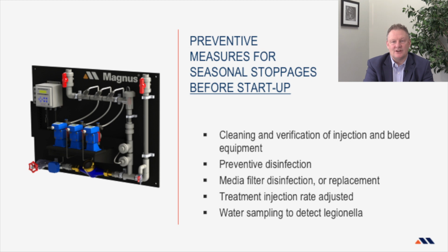Once the system is restarted, it is important to disinfect with an oxidant, such as chlorine or bromine. Stagnant water left over in the system may have biofilm, which must be removed before startup, as it can become a location for Legionella to grow. Once the cooling tower is operating, treatment conditions must be reestablished quickly and maintained throughout the warm season. Please keep in mind, evaporation rates will be lower in the first few weeks, which means that the treatment dosage rates must be adjusted accordingly.